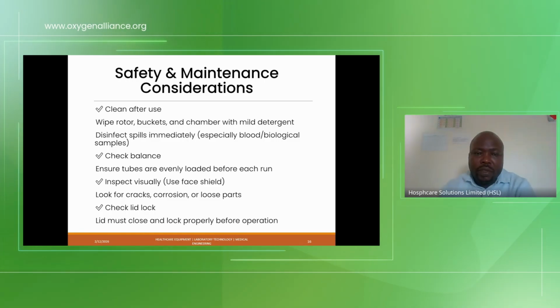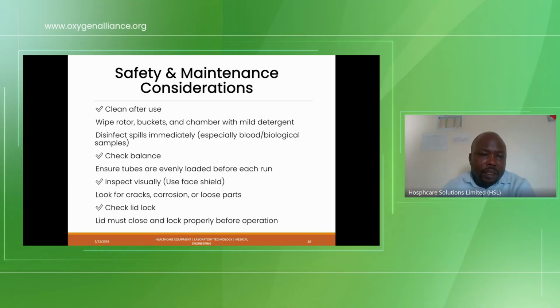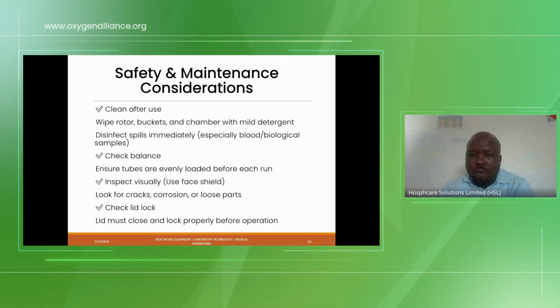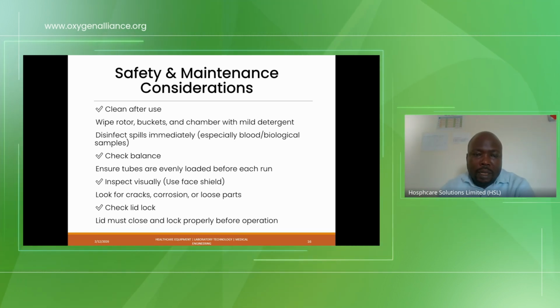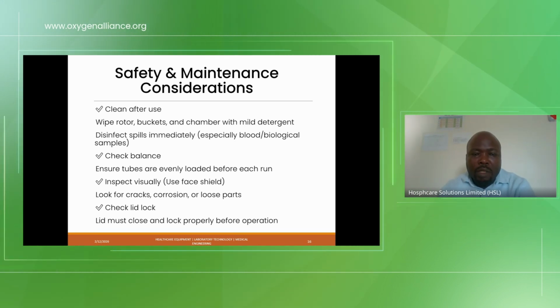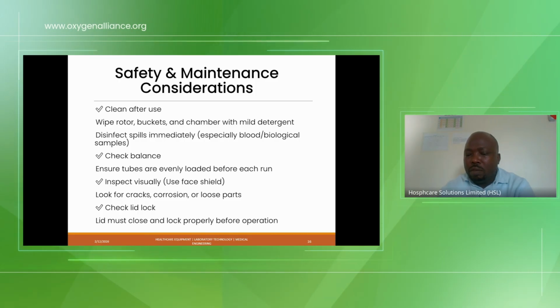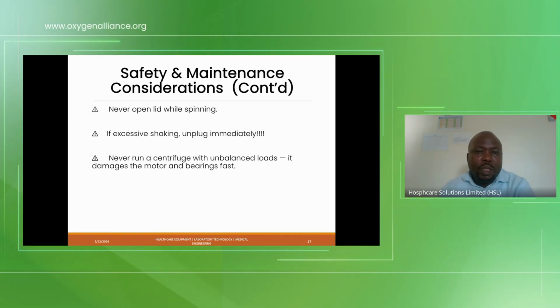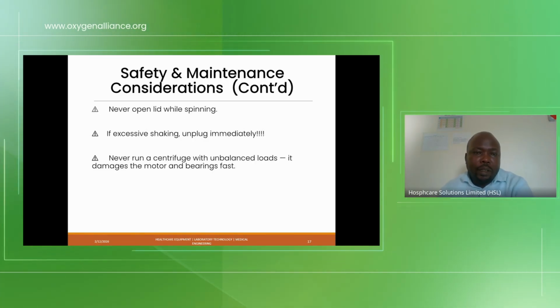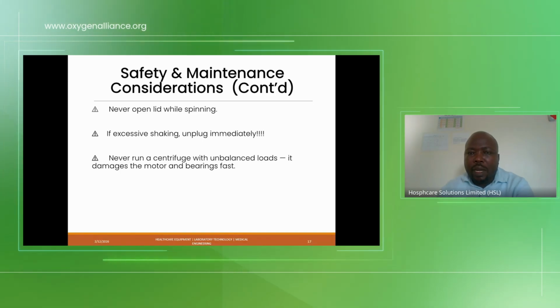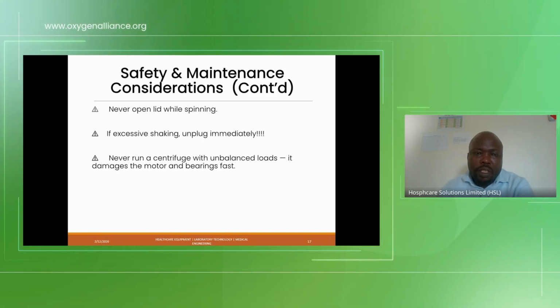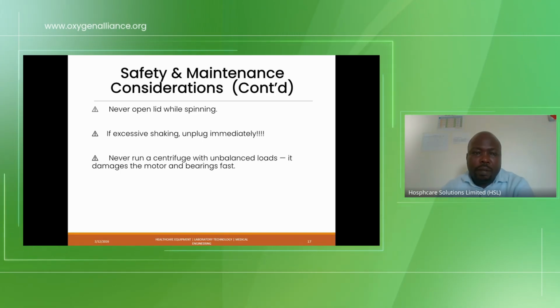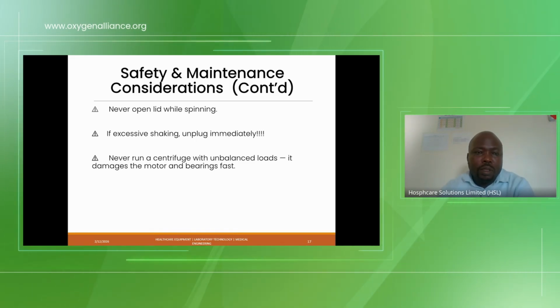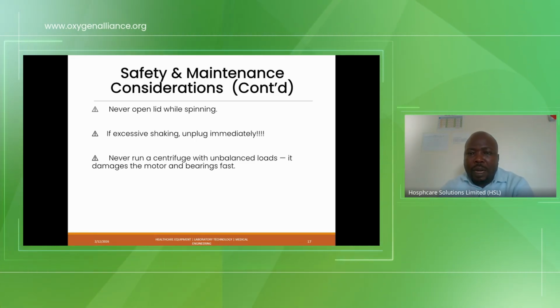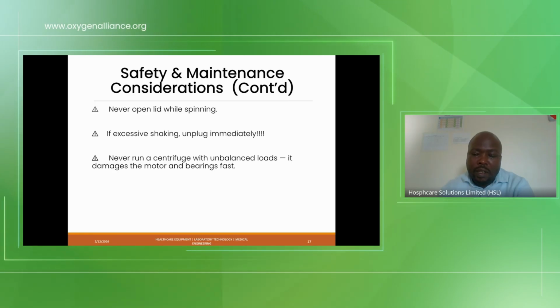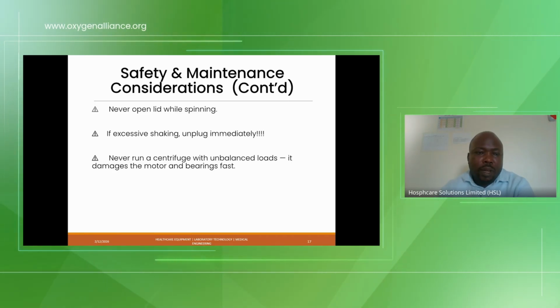You inspect visually, using the face shield, and look for cracks, corrosion, or loose parts. Check that the lid lock is functional. The lid must be closed and locked properly before operation. You never open the lid while the machine is spinning. If there is excessive shaking, unplug immediately. There is a reason for excessive shaking: it means the shock absorbers are worn out. Never run a centrifuge with an unbalanced load, as it creates wear and tear of the motor bearing.